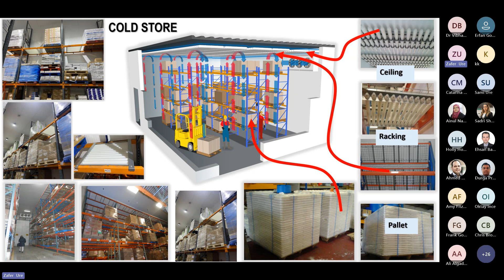And when surplus energy is available from the machinery, we freeze them. And when the heat and the load comes back, they hold back the refrigeration and absorb it like a sponge, soaking up the heat in the cold room. So therefore, we are in charge of when to run the refrigeration and when not to run. That's crucial for renewables, because we want to capture as much renewable energy as possible.